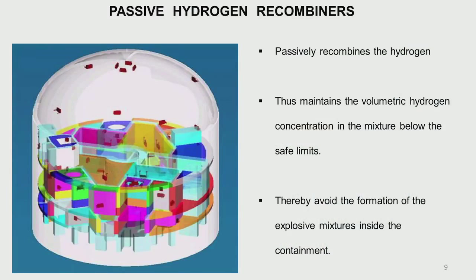In our reactors, we design so that hydrogen in any compartment does not accumulate beyond safe limits — and should it accumulate, we have hydrogen recombiners by which hydrogen is mixed with oxygen and becomes water. This should happen in a passive manner. We have two boiling water reactors at Tarapur similar to the Fukushima design, but we have hydrogen recombiners there. Unfortunately in the Fukushima reactor, these recombiners were not in operation.